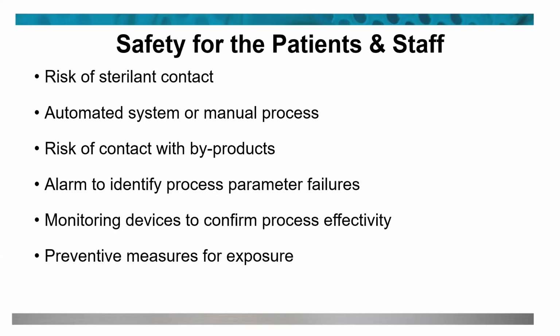Some of these machines, the sterilant is already injected and then they'll test for moisture. And some of them, they test for moisture right away and then your sterilant isn't put in if it detects moisture. So you're actually saving some money on your sterilant by having that happen.